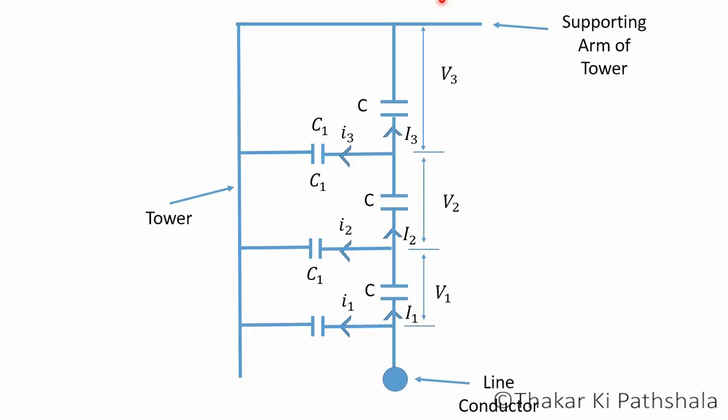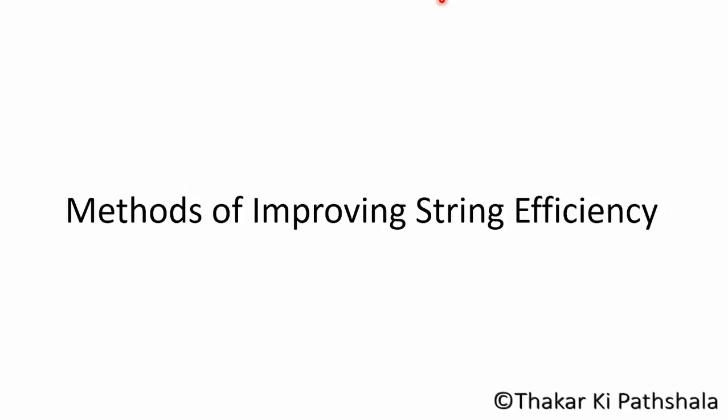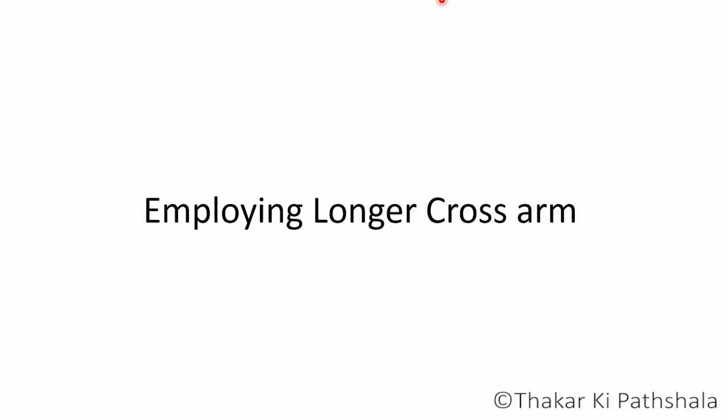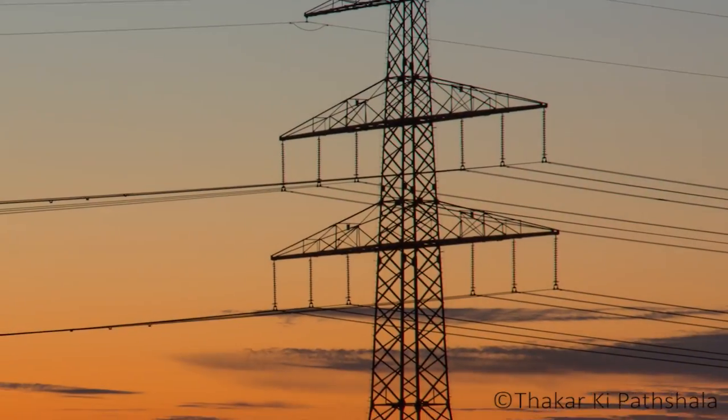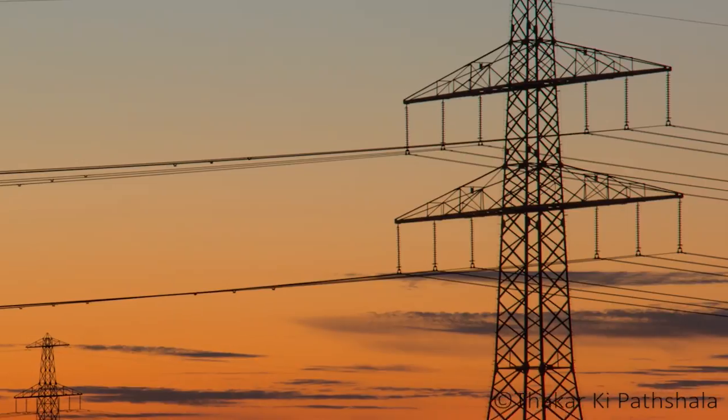So shunt capacitance has done its damage. Now it is up to us to compensate for this, and as engineers, we can find one way or another to solve these problems. There are three methods by which we can actually improve string efficiency. The first method is by employing a longer cross arm. Due to shunt capacitance, the charging currents are flowing to the ground, and as we go upward, the value of charging current through each unit decreases.